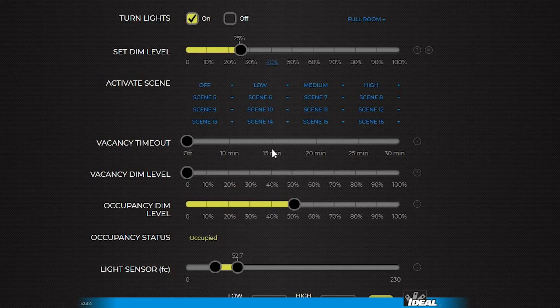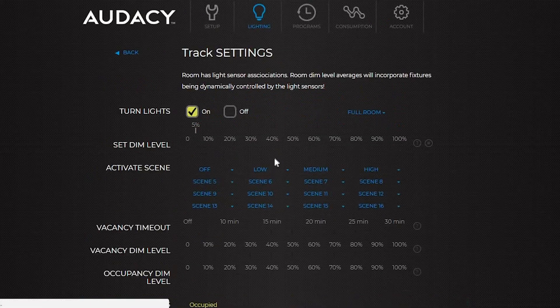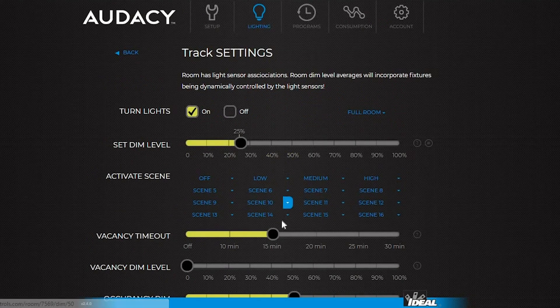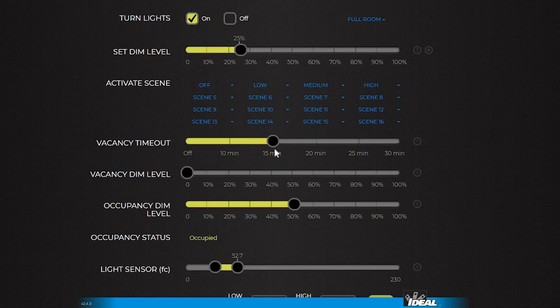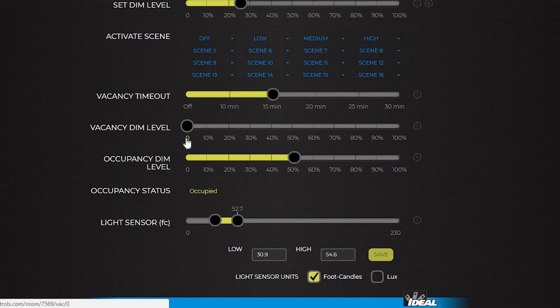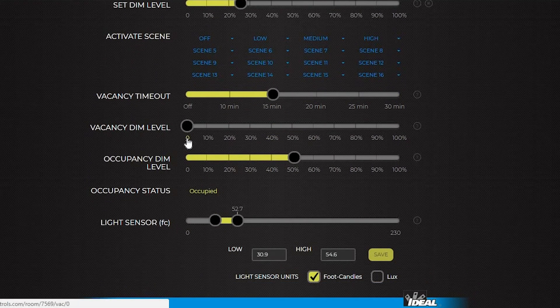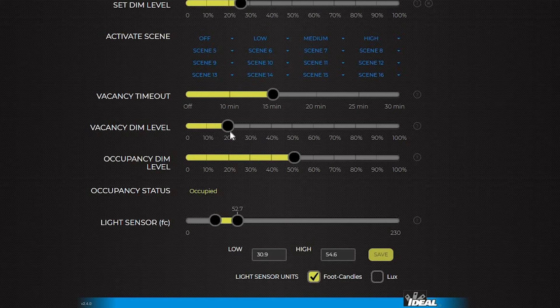This sets the vacancy timeout, which is how long after the motion sensor last reported movement that the lights will turn off automatically. The vacancy dim level is the level the lights should go to when the room becomes unoccupied. For example, in a hallway where the light should not turn completely off, set a vacancy dim level for when the hallway becomes unoccupied.